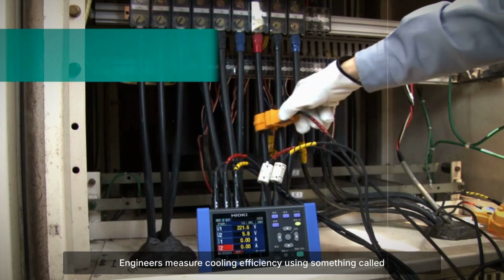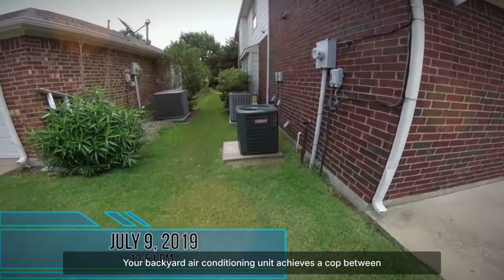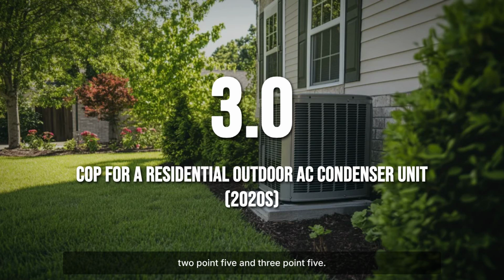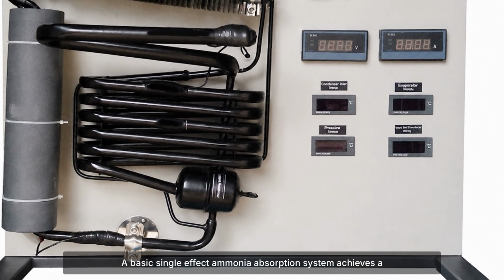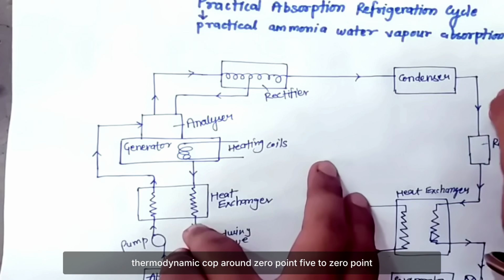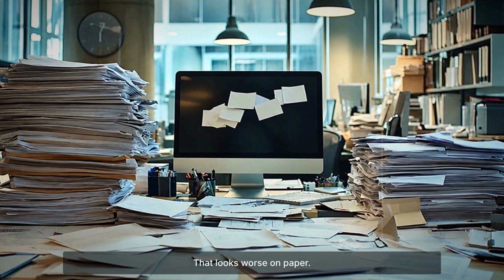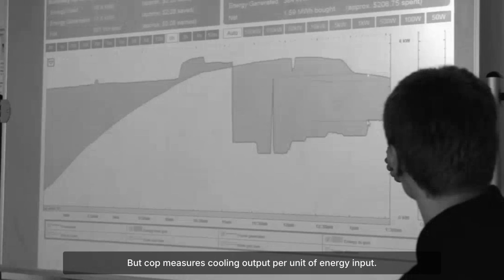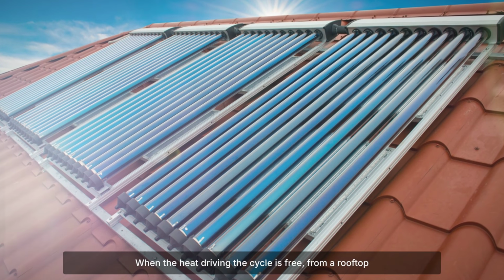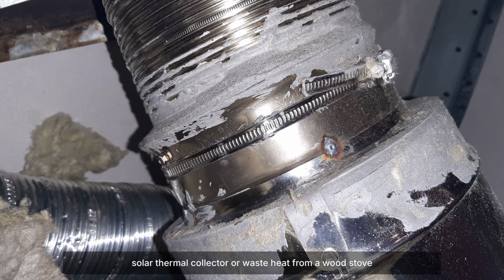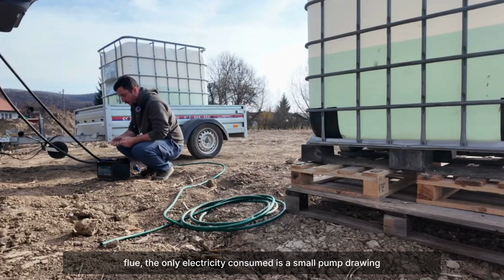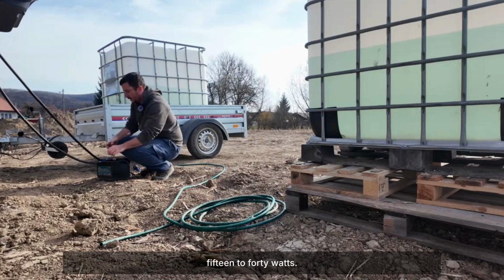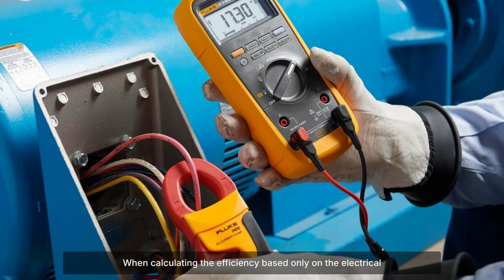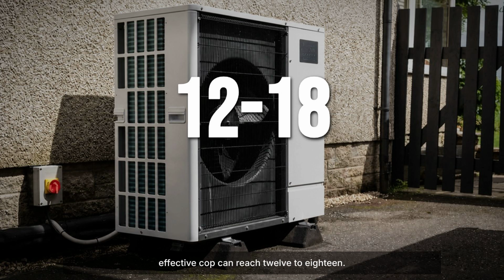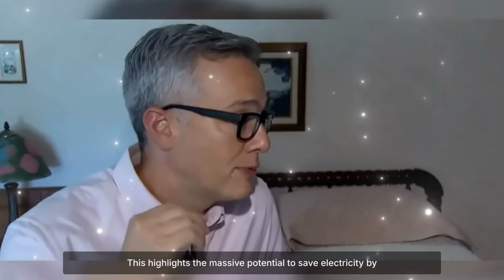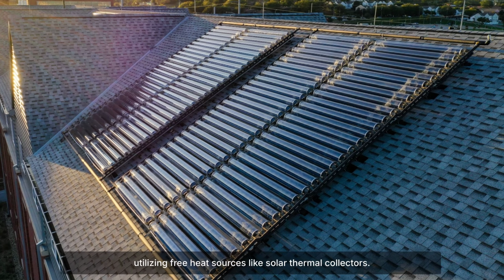Engineers measure cooling efficiency using something called coefficient of performance. Your backyard air conditioning unit achieves a COP between 2.5 and 3.5. A basic single-effect ammonia absorption system achieves a thermodynamic COP around 0.5 to 0.7. That looks worse on paper. But COP measures cooling output per unit of energy input. When the heat driving the cycle is free from a rooftop solar thermal collector or waste heat from a wood stove flue, the only electricity consumed is a small pump drawing 15 to 40 watts. When calculating the efficiency based only on the electrical power needed to run the small circulation pump, the effective COP can reach 12 to 18. This highlights the massive potential to save electricity by utilizing free heat sources like solar thermal collectors.